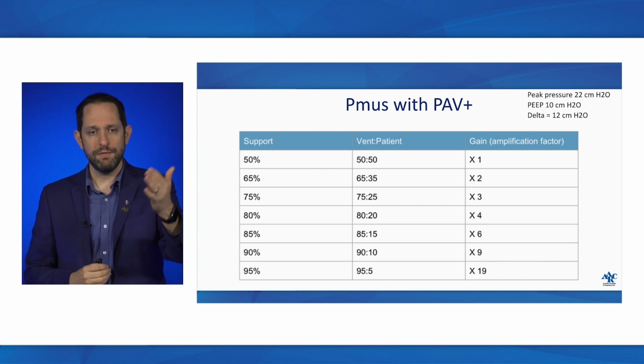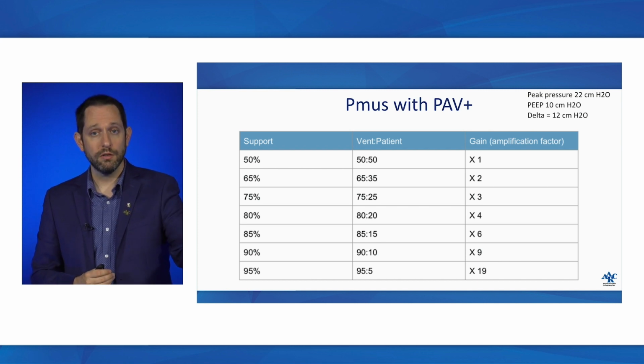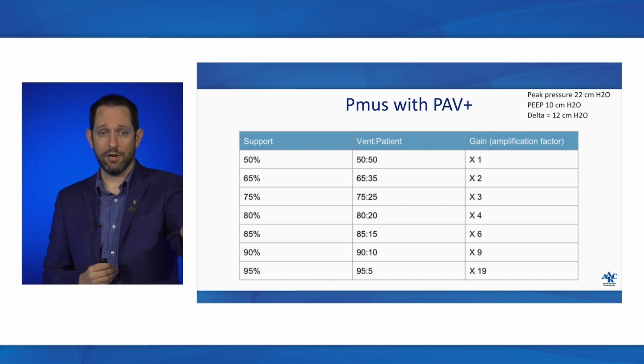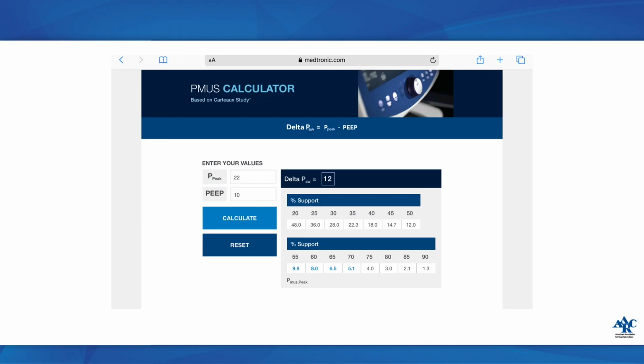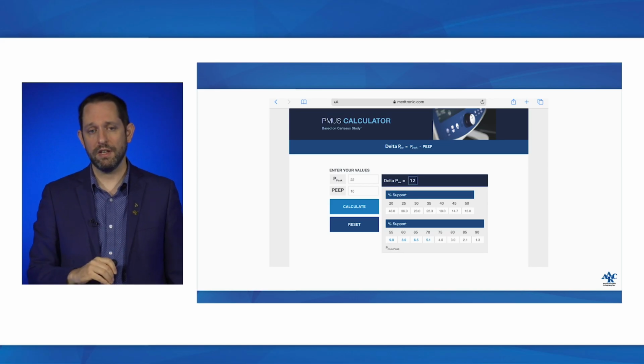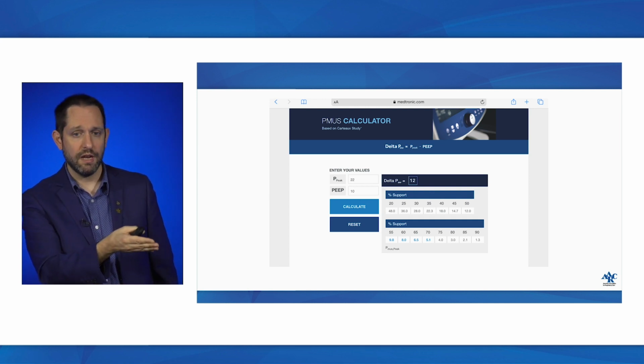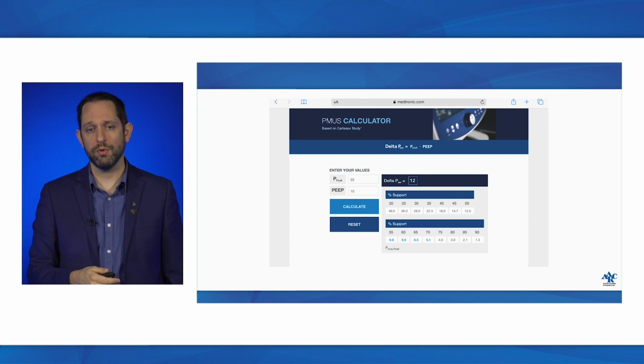Now, if you want this to be sort of simplified, you can Google PMUS calculator and you will find a calculator that can do this. Medtronic is the company that makes this calculator and makes the ventilator that has PAV Plus as a mode. If you type in PMUS calculator Medtronic, you will find this page where you just input the values that I just mentioned, 22 of peak pressure, PEEP of 10, and then you can see at every percent level what the work of breathing by the patient would be. So you know the delta pressure by the ventilator, and then you just look and see what percent support you have them at, and as you can see, 50% is 12 in this example, so you would probably increase the support to get them down into a lower level.